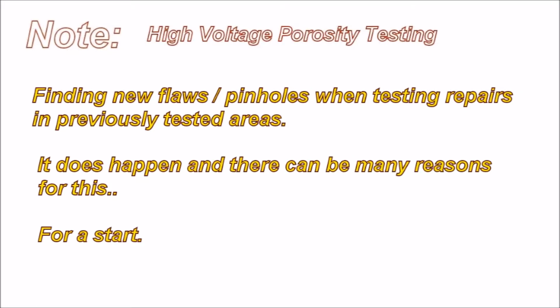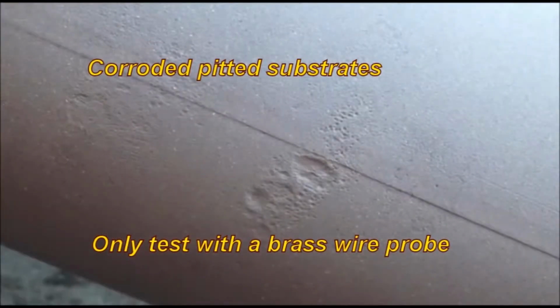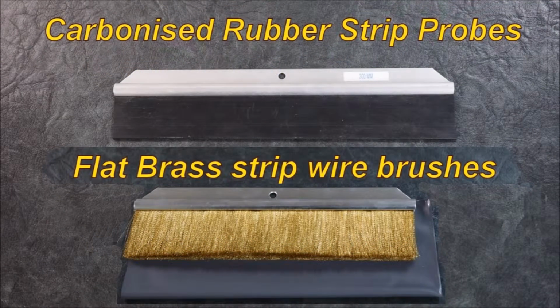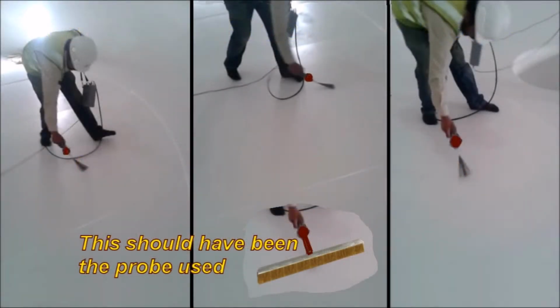For a starter, let's look at some of this. Heavily corroded substrates: only test with a brass wire probe. These fall into the holes. The carbonised rubber strip probes will not fall into the indentations like a brass strip wire probe will. This should have been the probe that was used here, not a little fan brush. As you can see, there's going to be a terrible amount of missed areas, and on retesting you'd most likely find all the spots not covered before.